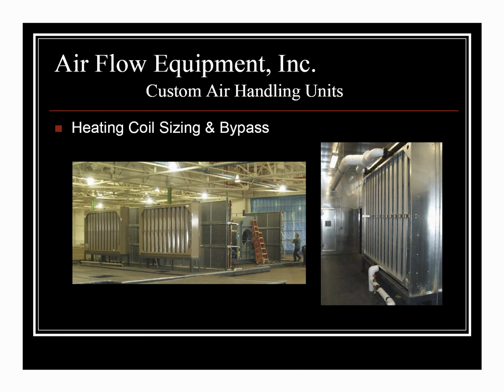If that is a concern, one of the things we have started to do, as you can see on this integral face and bypass, is put a bypass damper either below or above the coil, which accomplishes a couple things. Even with an integral face and bypass, a steam coil in particular, maybe you can't modulate it enough and you're still getting a little overheating in the space. You can open the other bypass damper below the coil, bypassing more air, not going through the coil, leading to better control. And using bypass dampers like that, you can throw them open when you don't need heating, reducing pressure drop through the system, saving the customer energy and cost.